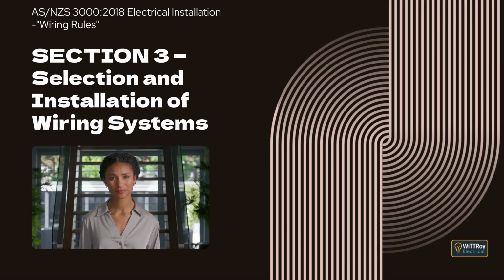Clause 3.4.3, Conductors in parallel. This clause explains how current carrying capacity is determined when conductors are connected in parallel. Where circuits use parallel multi-core cables or groups of single-core cables, the total current carrying capacity may be calculated as the sum of the capacities of the individual cables, provided certain conditions are satisfied. The cables must meet minimum size requirements, and the grouping of cables must not reduce their ability to cool in air or in the ground.